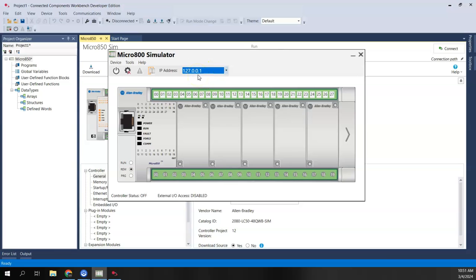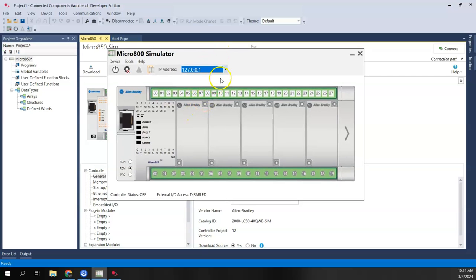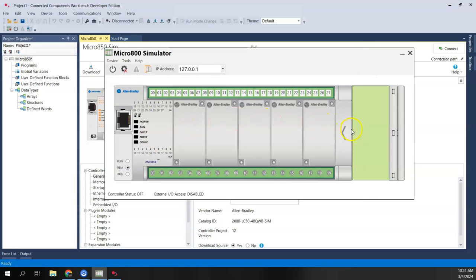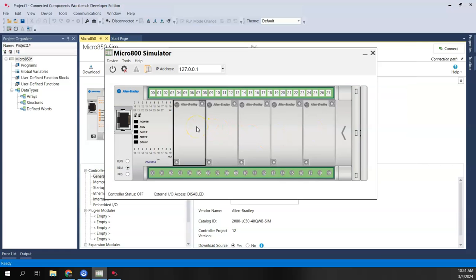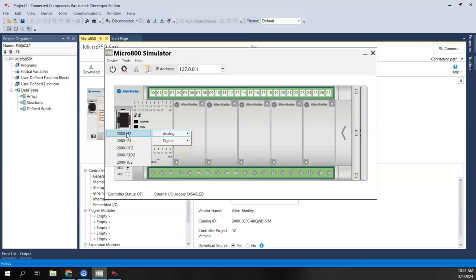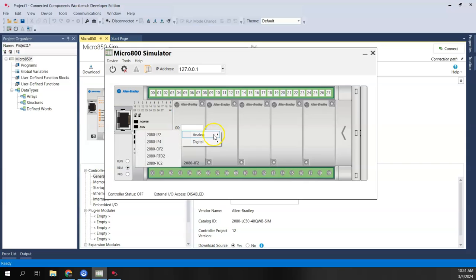We'll stick with 127.0.0.1. I do have five plug-in module slots and the ability to add expansion I/O — the 850 line gives you both. If I want to add a plug-in to this simulated controller, I can right-click on one of the plug-in modules and choose analog or digital. I'm going to add an analog input — the IF2 — in the first slot, and an analog output — the OF2 — in the second.